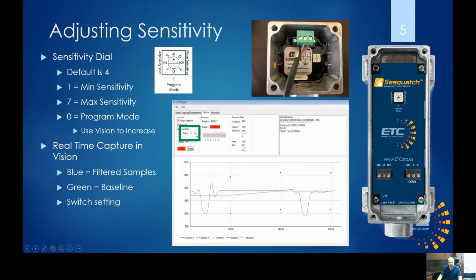This one's on the default of switch position 4. What that does is that sets this threshold both above and below the baseline. So it doesn't really matter the polarity of the signal. If it goes up or down and goes outside these red dots, like you see here, we close the switch. And so in Vision, you can see the switch closed here, but in normal operation, we would close the output switch, denoted by the SIG pin. And I'll show you that in the wiring.